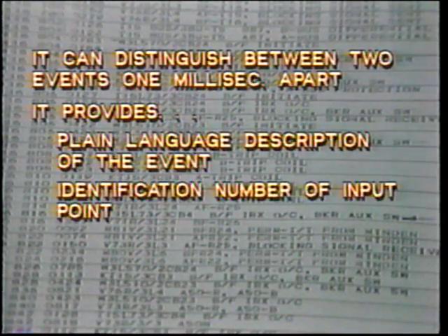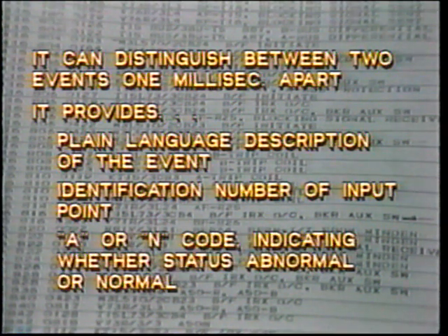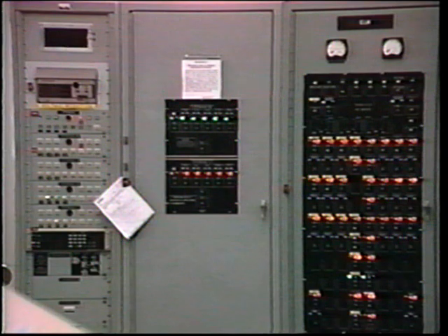the identification number of the input point, and an A or N code indicating whether the status of the device became abnormal or normal. In some installations, instead of a specific SER, the status is monitored by telemetering, that is, the SCADA system.